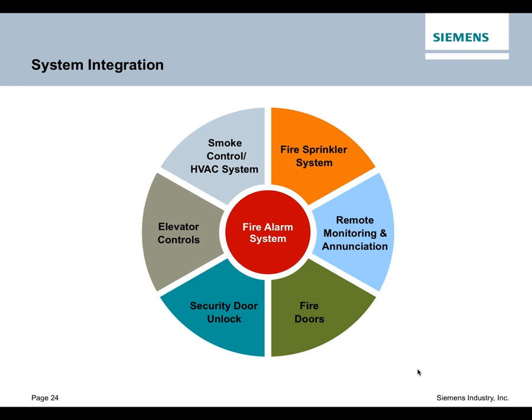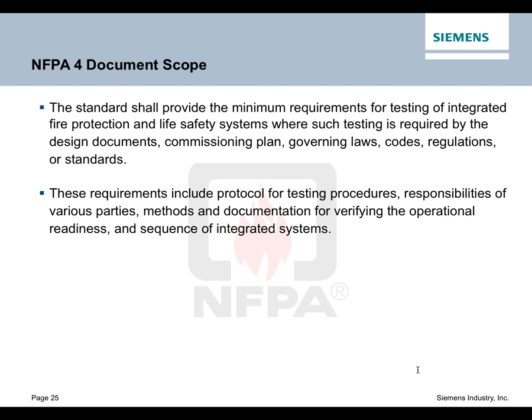And we have a visualization here to show you why the fire alarm system is oftentimes looked at as the center of this. When you see the description above, or the visualization here on the slide, you'll see the fire alarm system in the center, but it connects, talks to, communicates, and interacts with all those things around the circle. Certainly the fire sprinkler system. We're looking at tamper switches, water flow switches. We may be activating solenoid switches on dry pipe systems. We have smoke control, elevators, door locks, all these other functionalities that you can see connected into it here. So that's why the fire alarm system is oftentimes in the center.